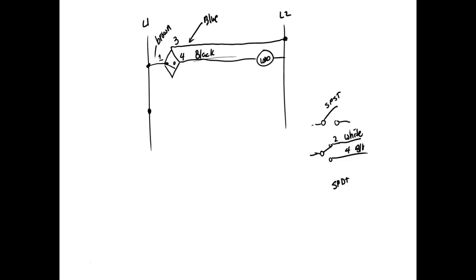So you'll have what we call a 4-wire sensor. The colors on a 4-wire sensor will be brown, blue, black, and white. On a 3-wire solid state sensor, they're going to be brown, blue, and black. On a 2-wire solid state sensor, they're going to be brown and blue.